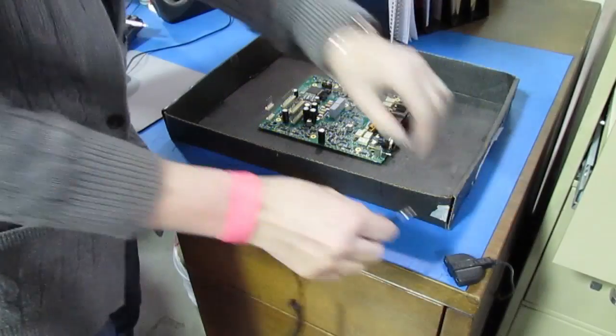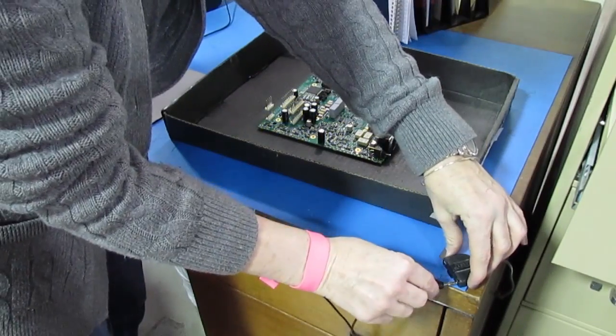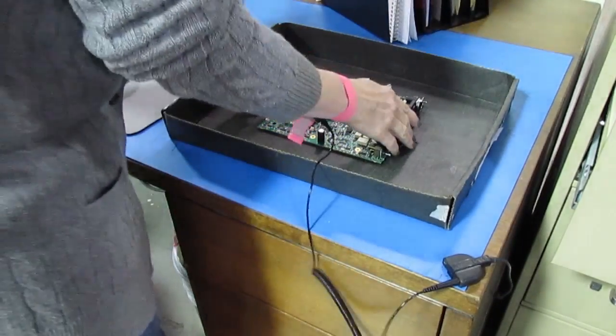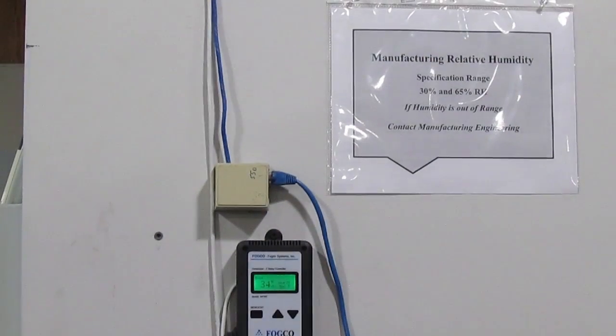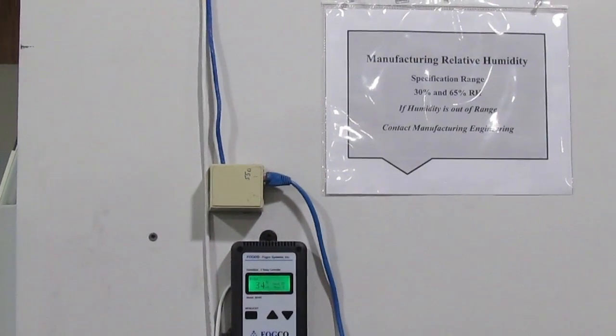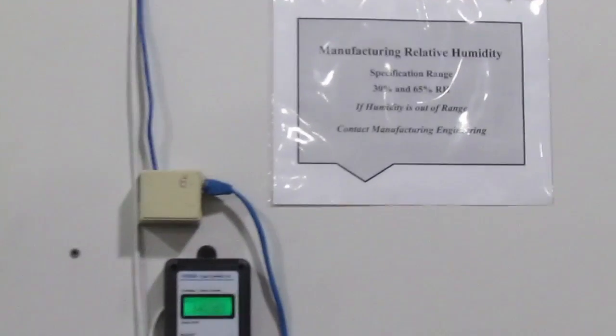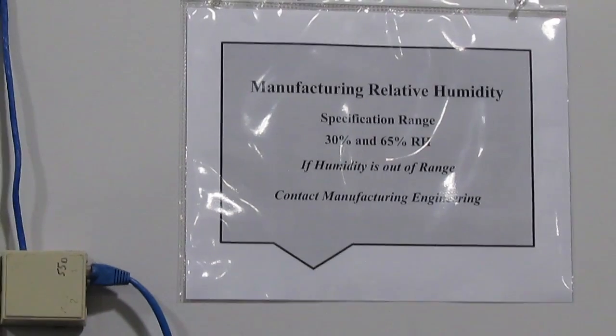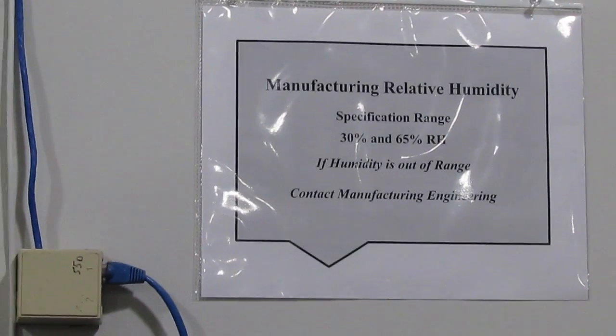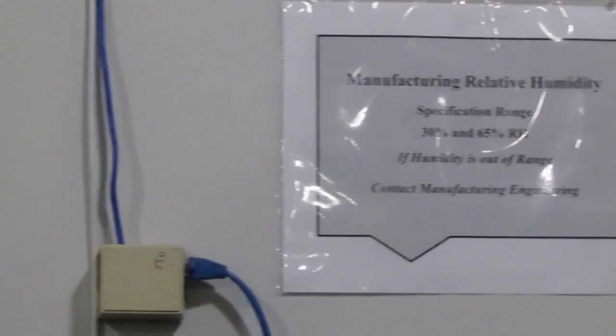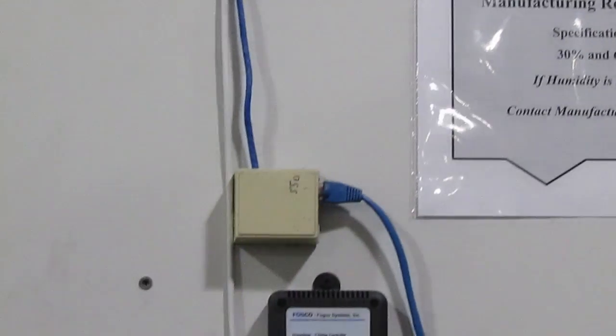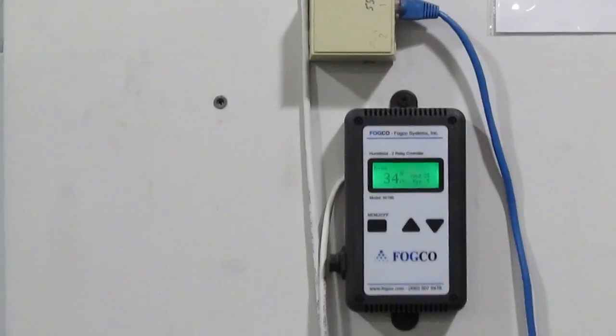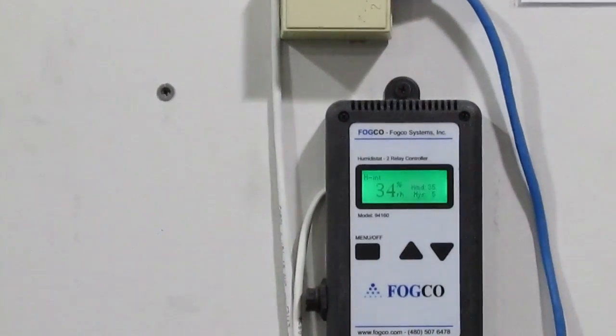We take a lot of measures to control ESD, and one of them is maintaining the right level of humidity in the air. If the air is too humid, it will shorten the life of our moisture sensitive devices. If the air is too dry, it will increase the risk of ESD damage.